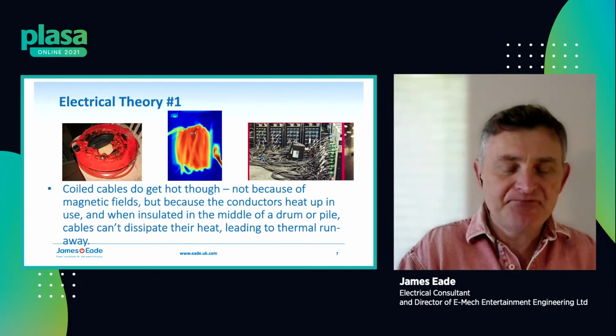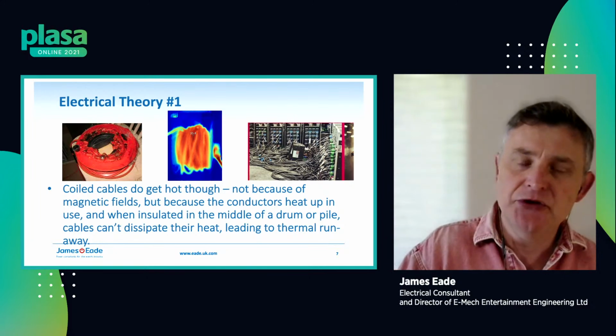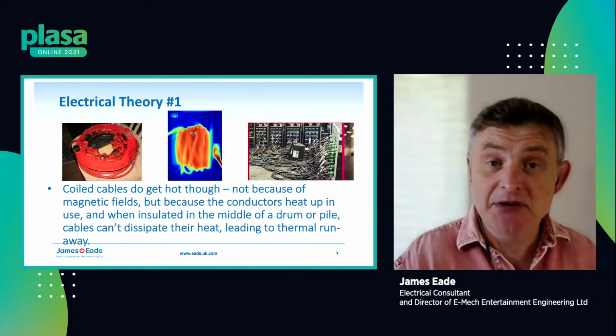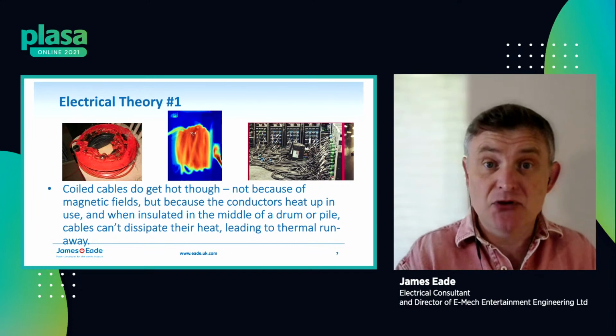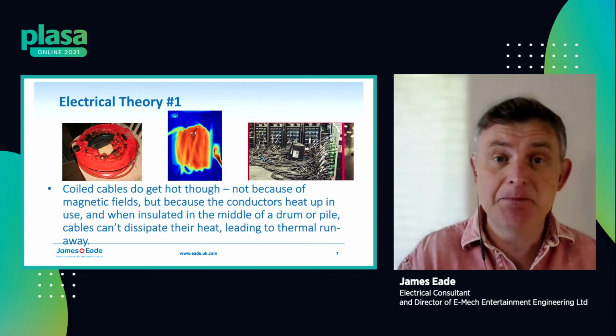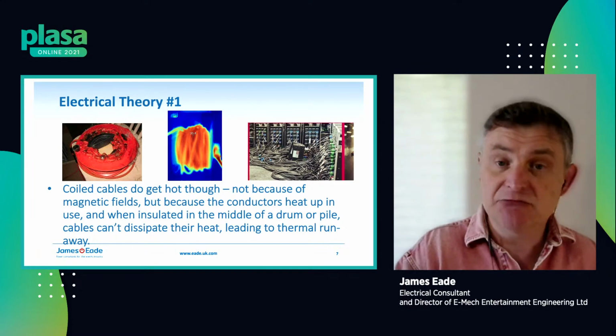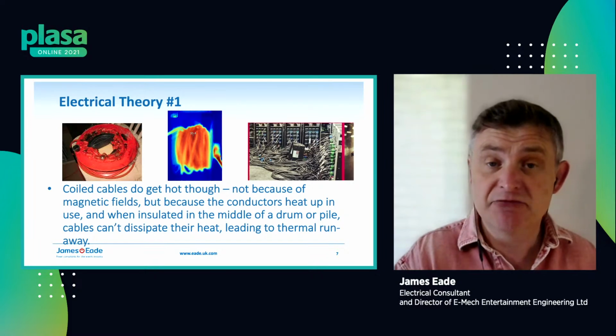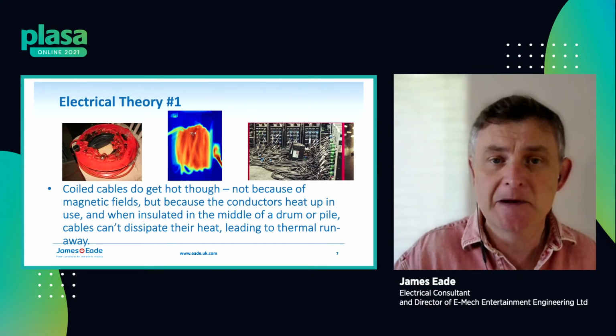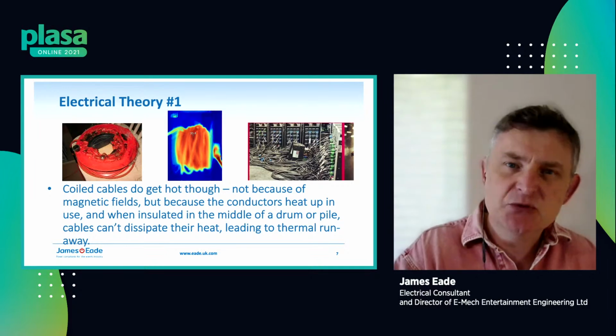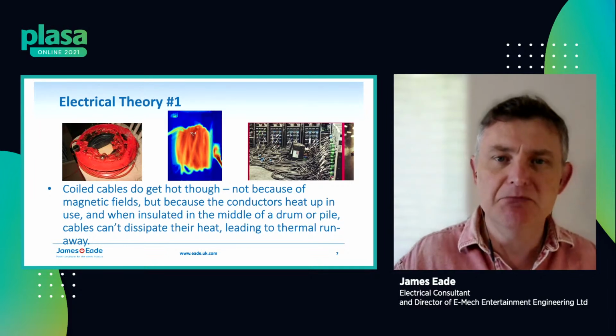So if you've got current flowing through the resistance, the cable will heat up, and if it's insulated by other cable on top, it can't dissipate its power. That makes the resistance increase because it gets hot, so the resistance of the conductor goes up, and that leads to thermal runaway. That's why cable drums melt.